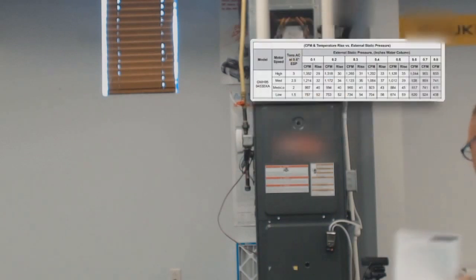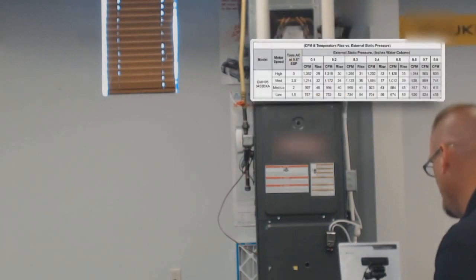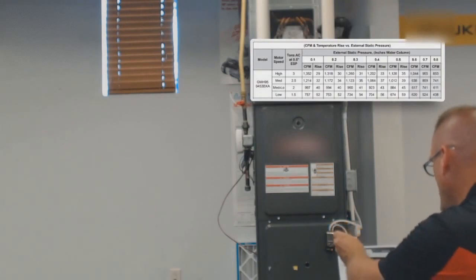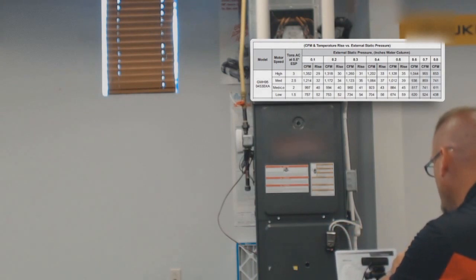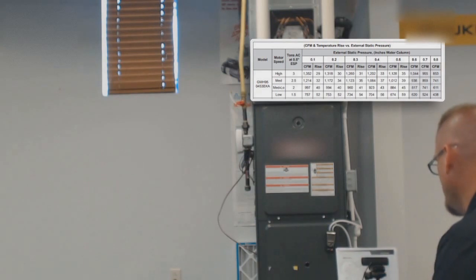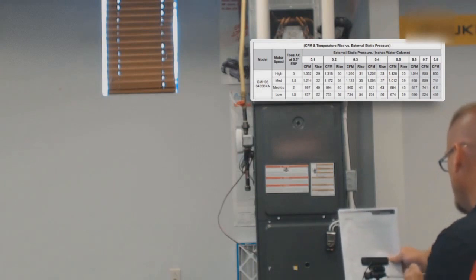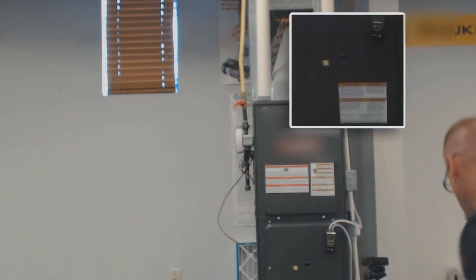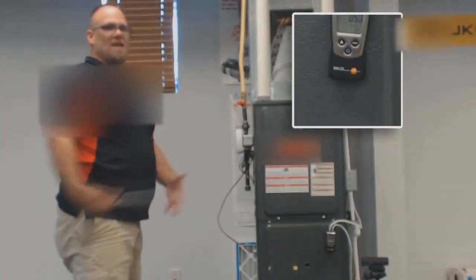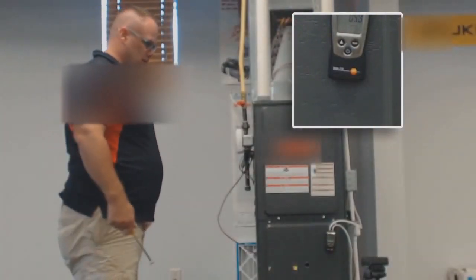If you look at the installation guidelines for the system that we're working on, we're on medium low, and 0.5 inches of water column gives us 884 for our value for CFMs. We've got a 2-ton system we're working with, and as the manufacturer specified, we're looking for 400 CFM per ton. 2 tons at 400 CFM per ton would give us 800 CFMs. So we're right at that value we need to be at.